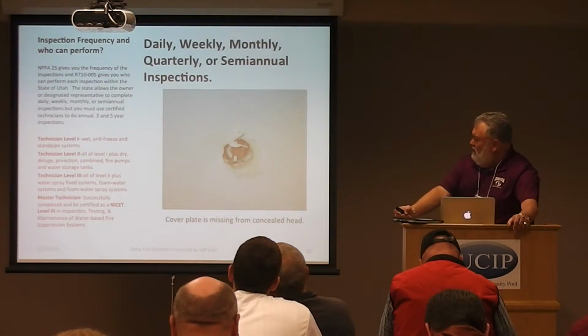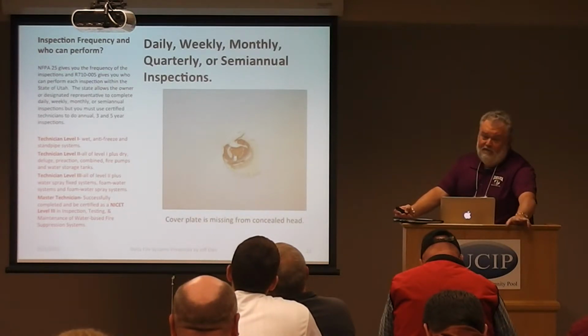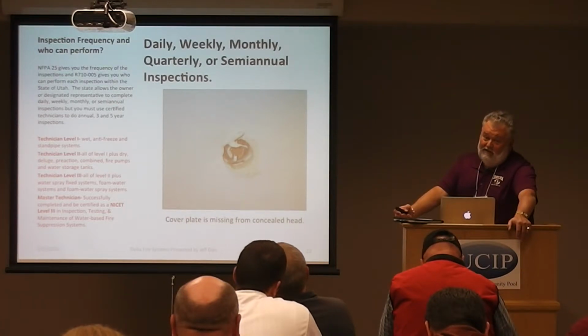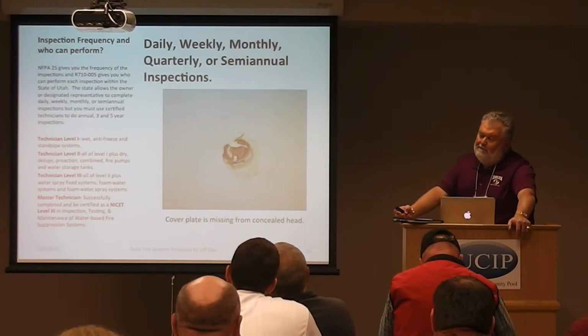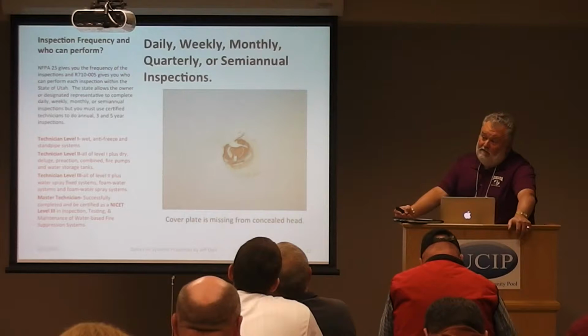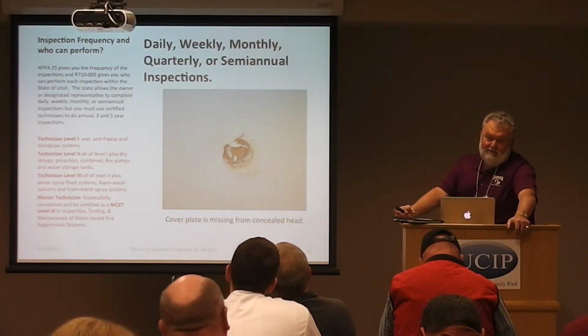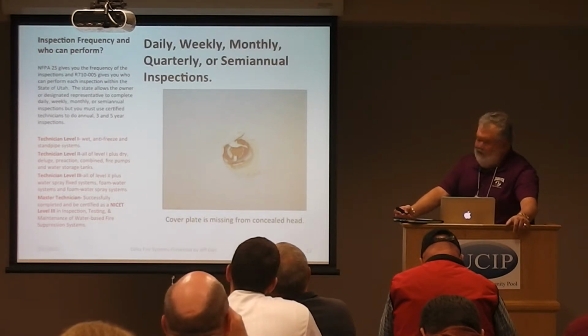A Tech Level 1 can do certifications on wet and antifreeze and standpipe systems only. Part of that certification is a written test that you have to take at the State Fire Marshal's office and have verification that you've done these in the past. When that was initially set up, it was set up as a closed book test. Some of the school districts and cities and counties wanted their own maintenance personnel to be able to do that. So, being involved in the political arena, they changed it to an open book test. And so there are people within counties and cities that are certified at different levels. That's one additional reason why there are different technician levels here.